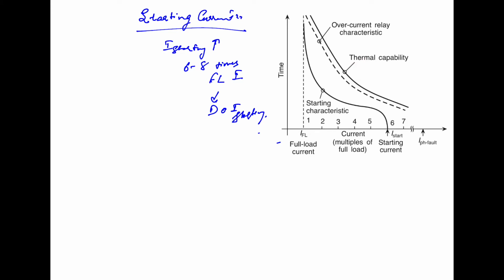So this will ensure that the protective relay does not operate during the starting of the motor, but positively it will operate when the load exceeds this motor's thermal capability.